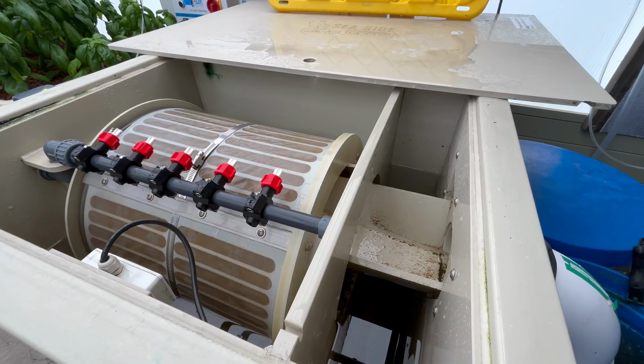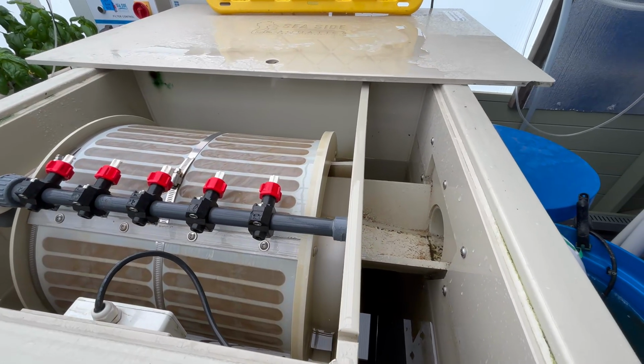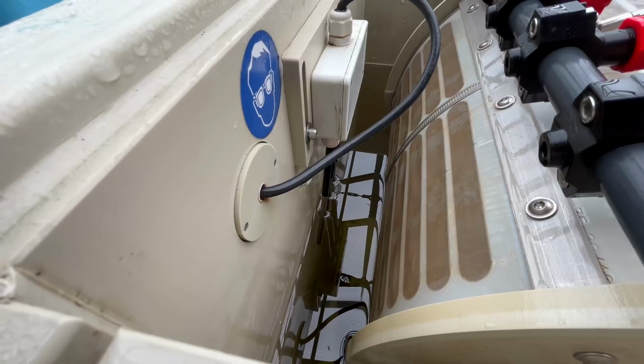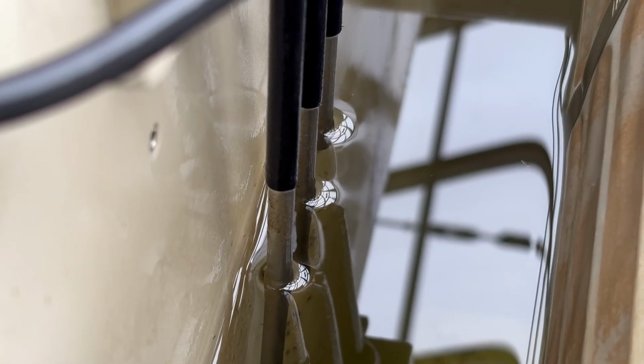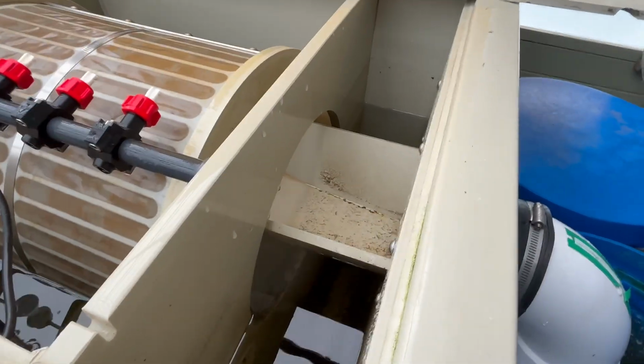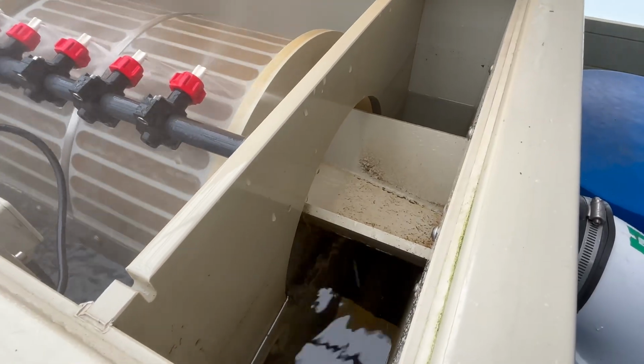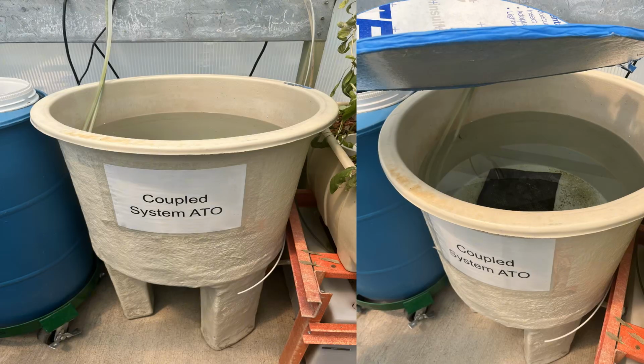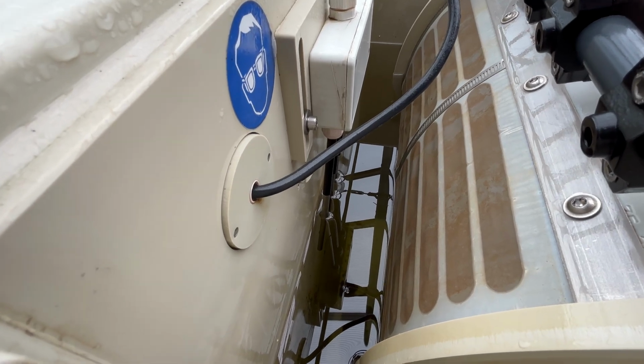Now, as the drum gets clogged up with detritus, flow will slow down and the water level will fall. After approximately 30 minutes, which is about the amount of time it takes for the probe to be uncovered, the water level will get too low and the sensor will trigger the spray bar to clean the drum. The water from the spray bar will raise the water level back to its standard position. Furthermore, an ATO system will keep the water level at the correct position with a separate sensor.